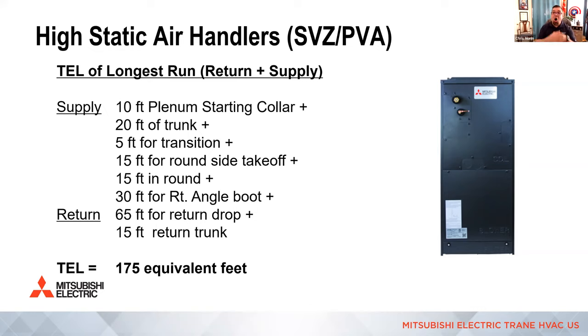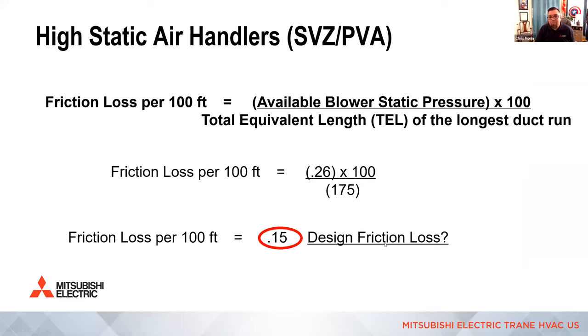So when you add up all of these numbers, it ends up being 175 feet. And that sounds like a big number, but it's not. I've designed systems with 400 or 500 feet of duct in equivalent length. All right. So don't be scared when you get these numbers. And in fact, this is really low when you talk about a whole floor in the largest, longest equivalent length.